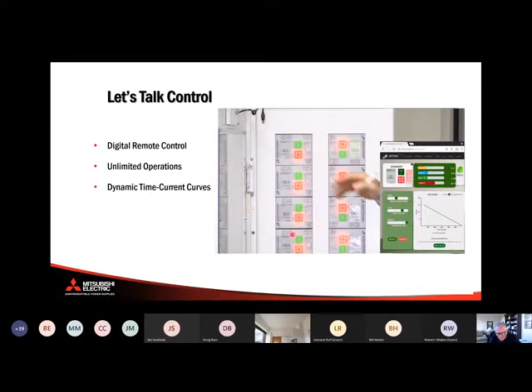As far as speed, the device opens so fast it's got a 3 microsecond round trip fault detection, which means it opens 16,000 times faster than a regular circuit breaker. That means your 100 amp circuit switch opens in 700 nanoseconds, and the 1200 amp circuit switch opens in 2 microseconds.